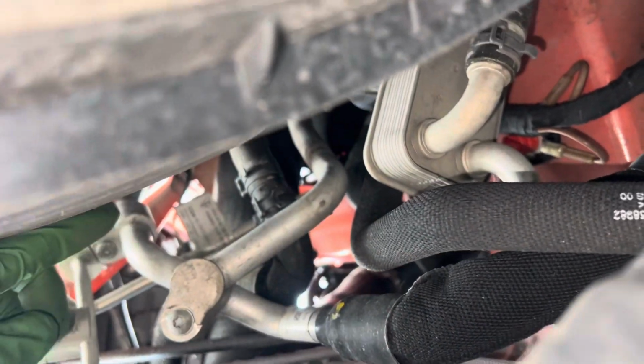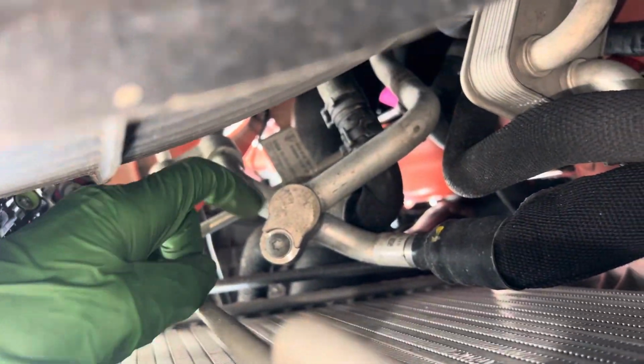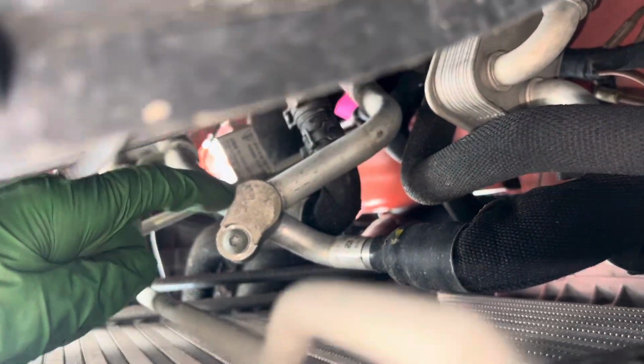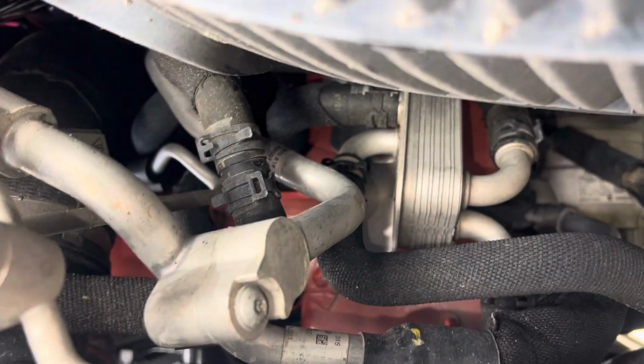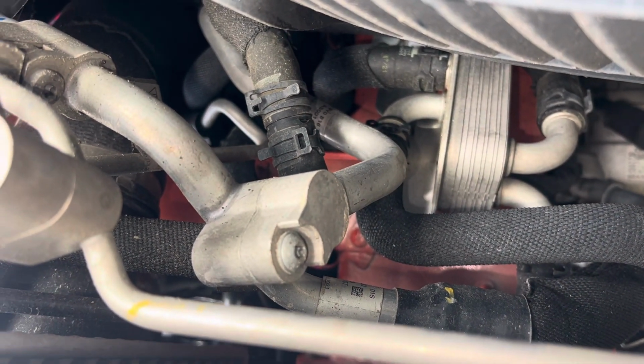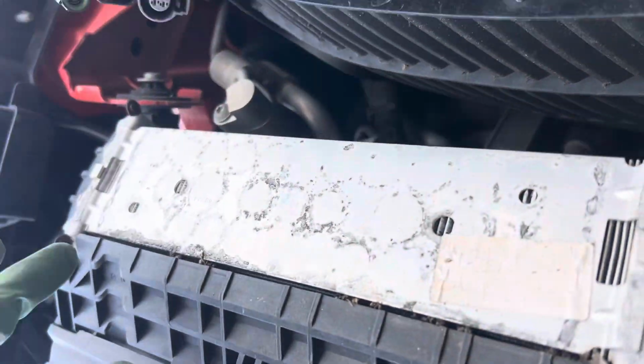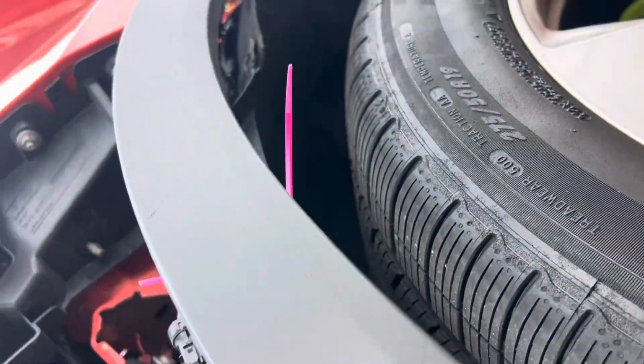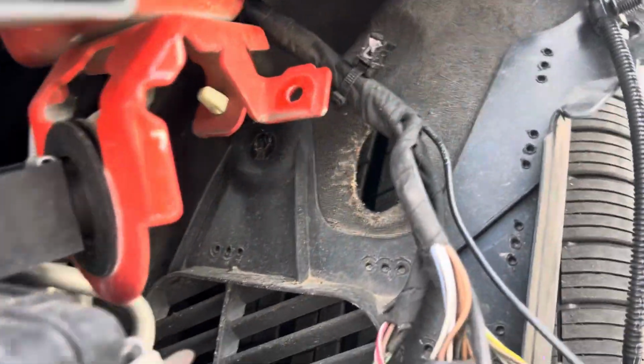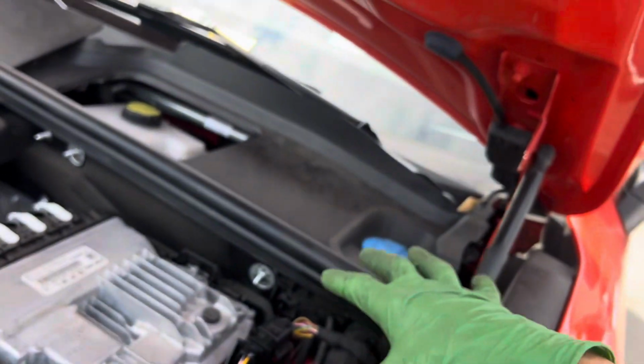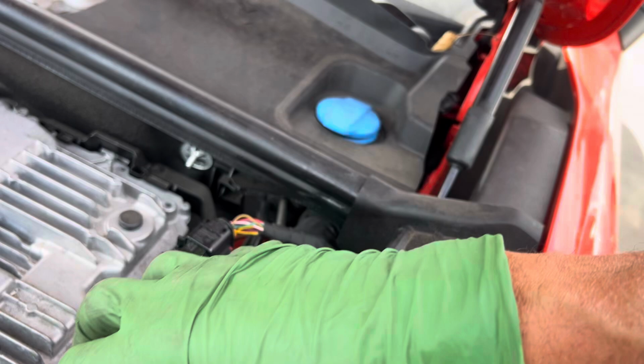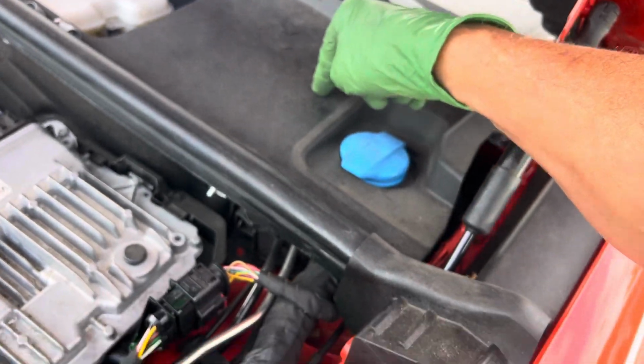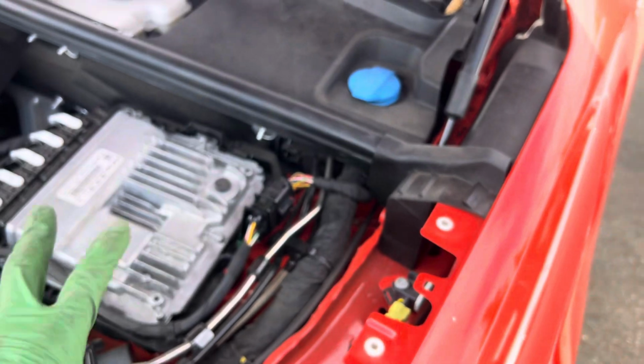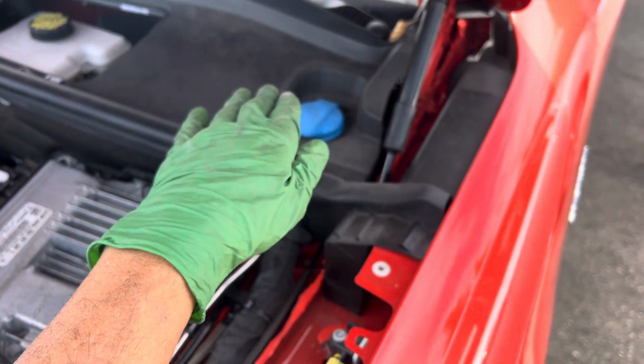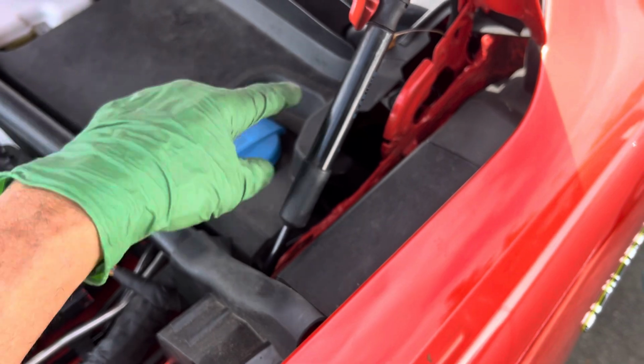You wouldn't know this because here's a straight pipe, goes straight over to here, but this is actually a Y right there. Another pipe going right there, your suction line, and that's off of a plate heat exchanger that will either have hot or cool glycol running through it, and it comes in from up here. So this is probably part of, there's a massive refrigerant in there going to this liquid plate heat exchanger, and I could see when it stabilizes and cools off, all the oil comes out of suspension, and this refrigerant line is probably high, has refrigerant.